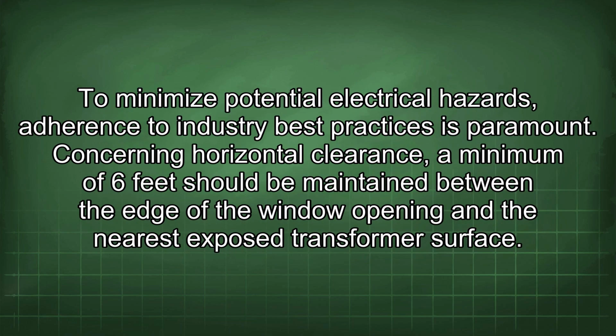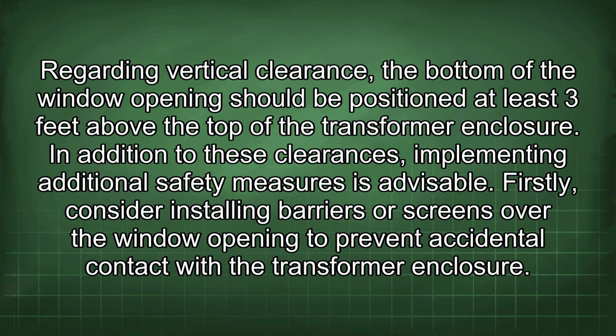To minimize potential electrical hazards, adherence to industry best practices is paramount. Concerning horizontal clearance, a minimum of 6 feet should be maintained between the edge of the window opening and the nearest exposed transformer surface. Regarding vertical clearance, the bottom of the window opening should be positioned at least 3 feet above the top of the transformer enclosure.